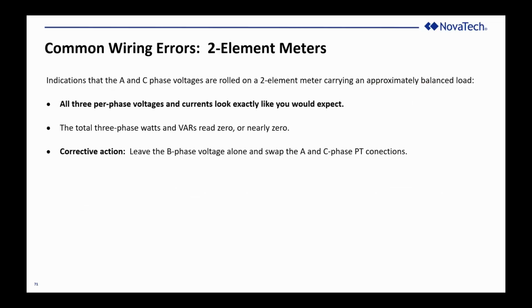Indication the A and C phase voltages are rolled: all 3 phase voltages and currents look normal, and the total 3-phase watts and VARs read 0, or nearly 0. So you can leave the B phase voltage alone, because in a 2-element wattmeter it's usually the B phase voltage that's grounded. For the same reason that you can always tell if I've rolled the neutral, because the neutral is going to be ground and the other 2 conductors are going to be hot, you can always tell that the B phase voltage has to be ground. So the 2 hot lines have to be A and C.